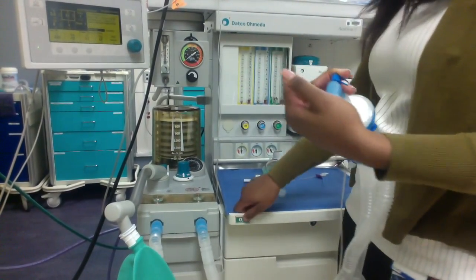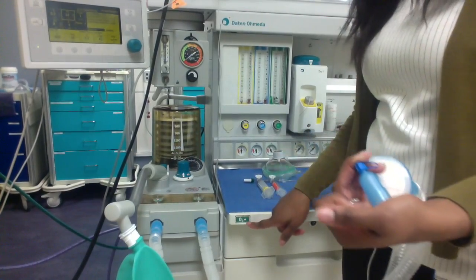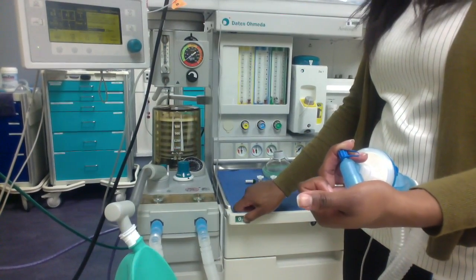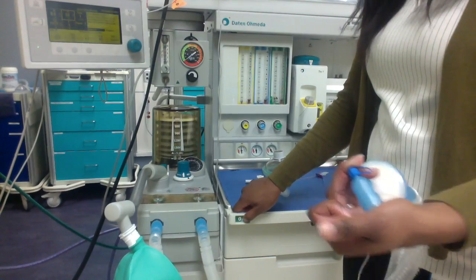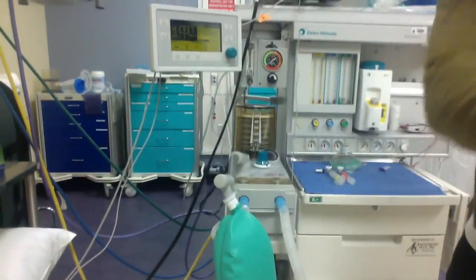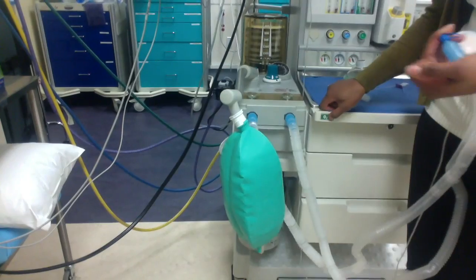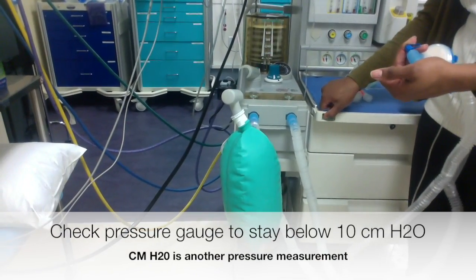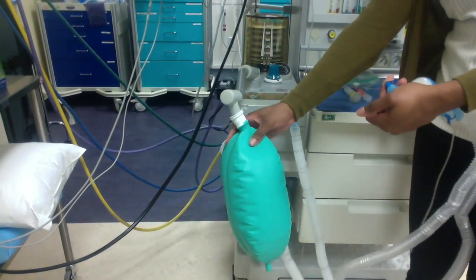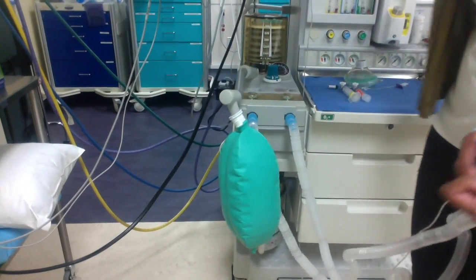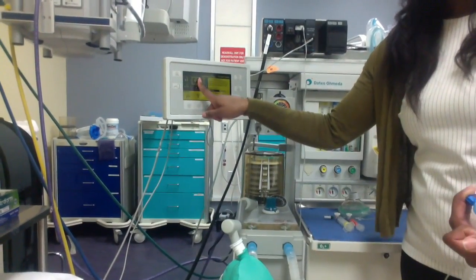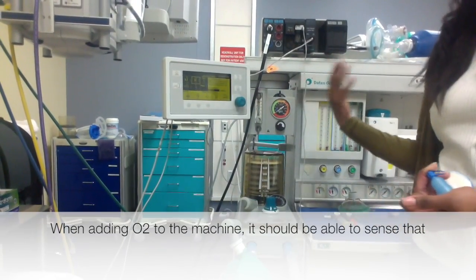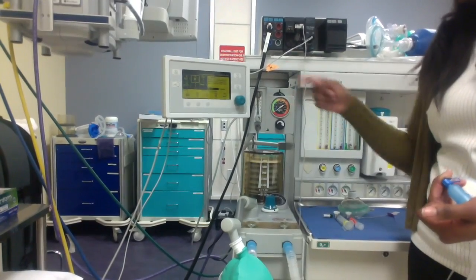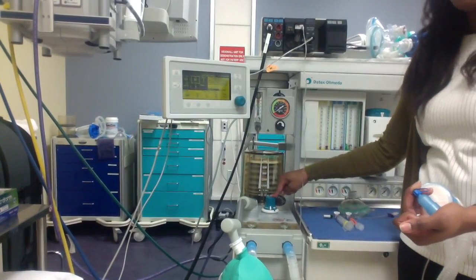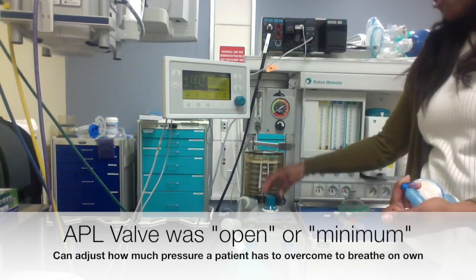So then what I would do is I would flush. This is my O2 flush button. I would flush the system with O2. And what I'm making sure is happening is that my circuit is not reading above 10 centimeters of water, that my bag is filling appropriately, and that here I'm reading at least 90% O2. I just want to be able to tell that my machine can read 90% of oxygen, and it does. That was all with my APL valve, which is your adjustable pressure limiting valve, open.